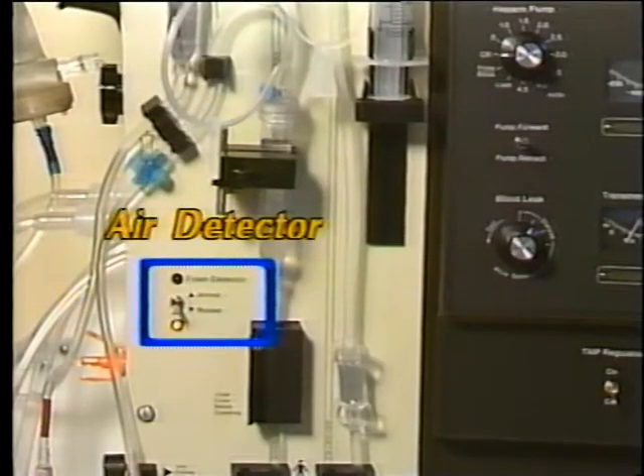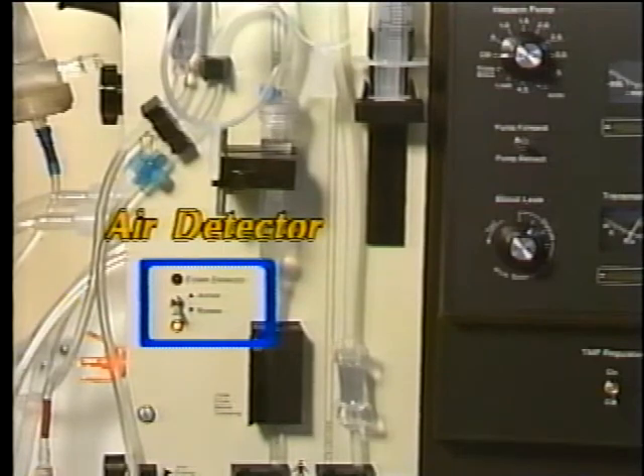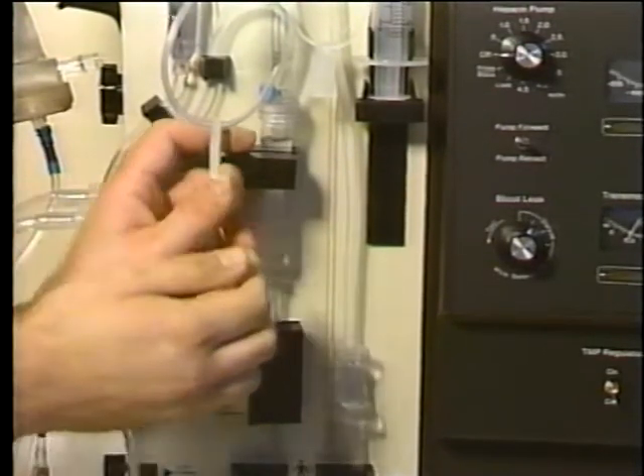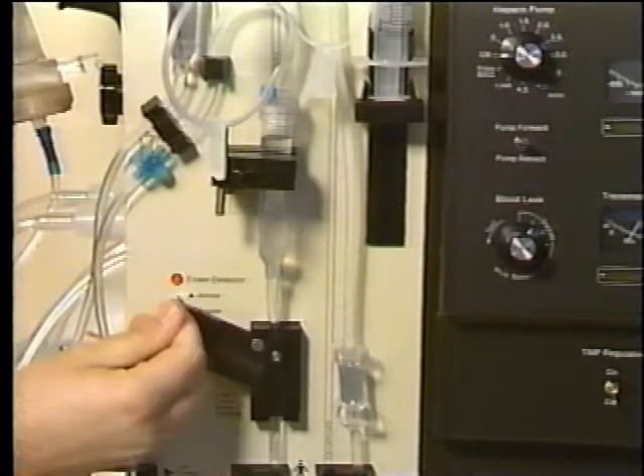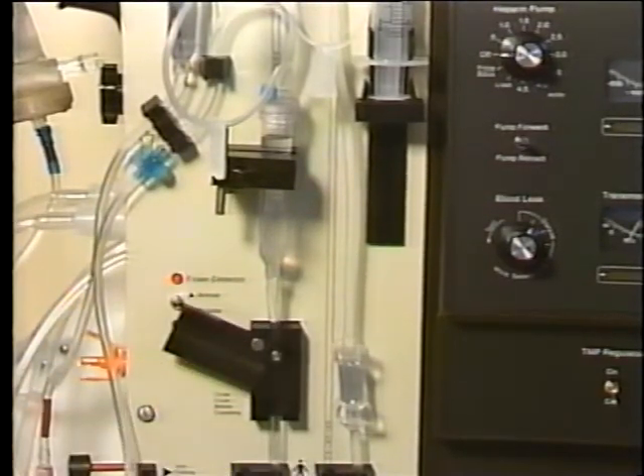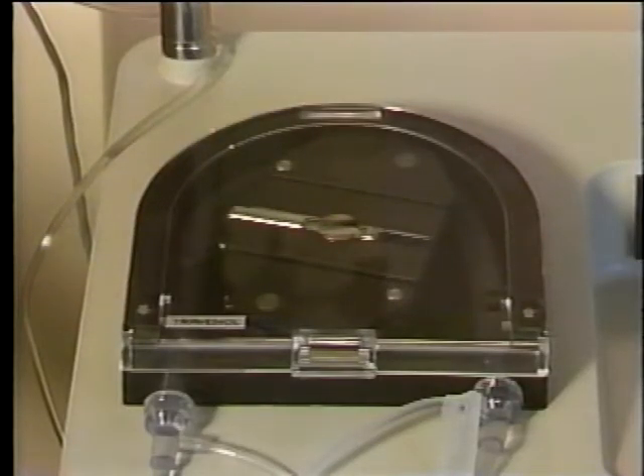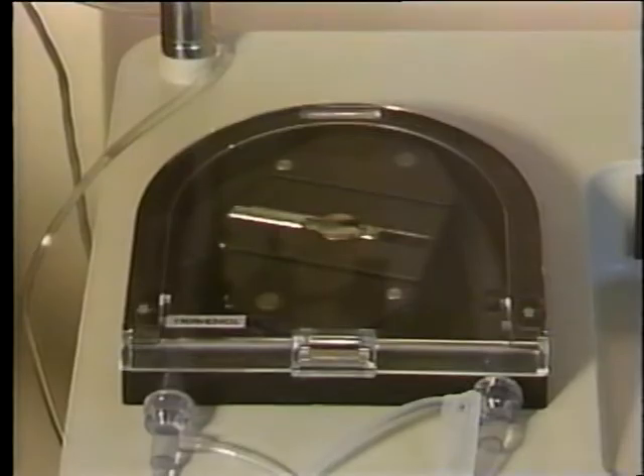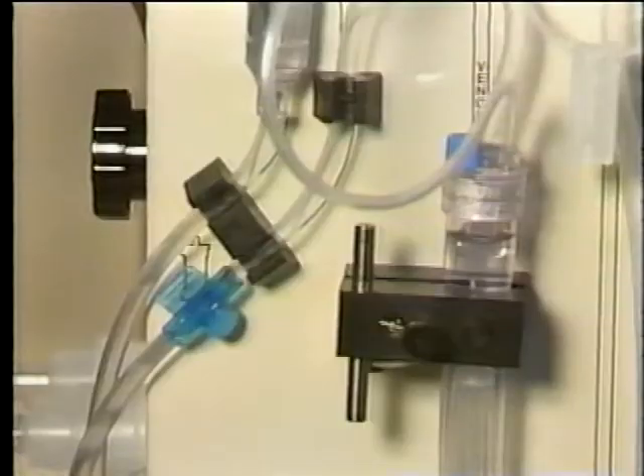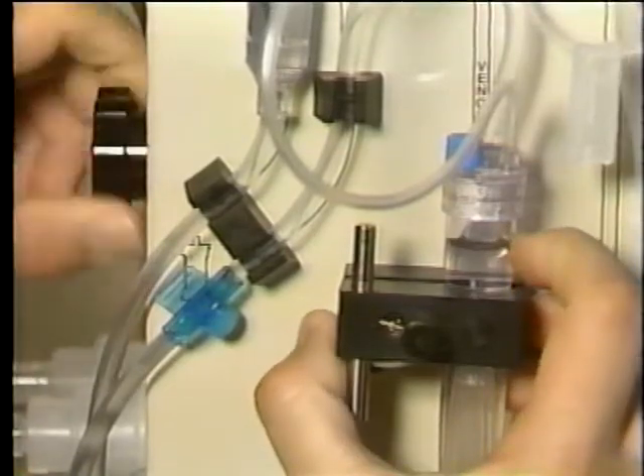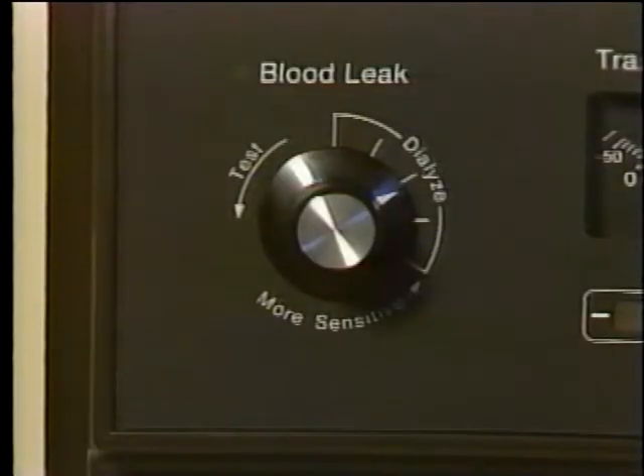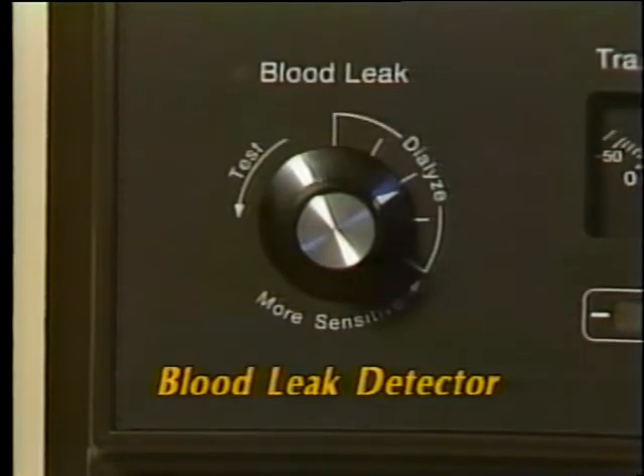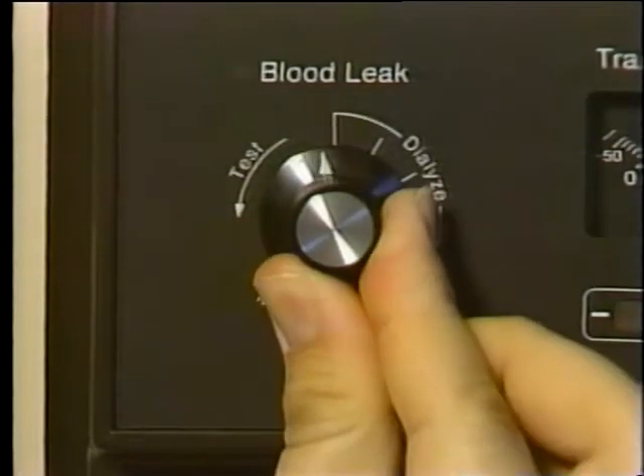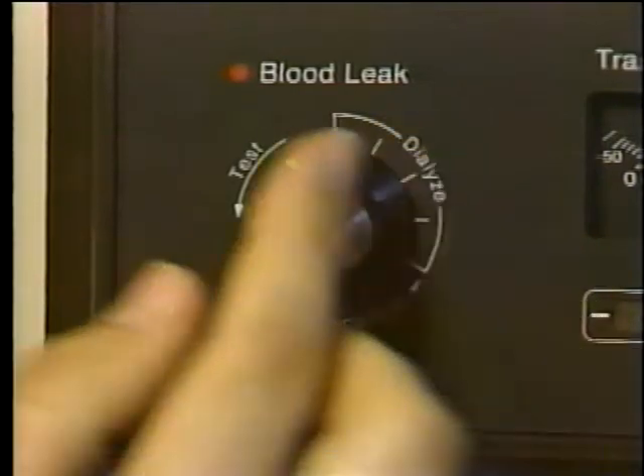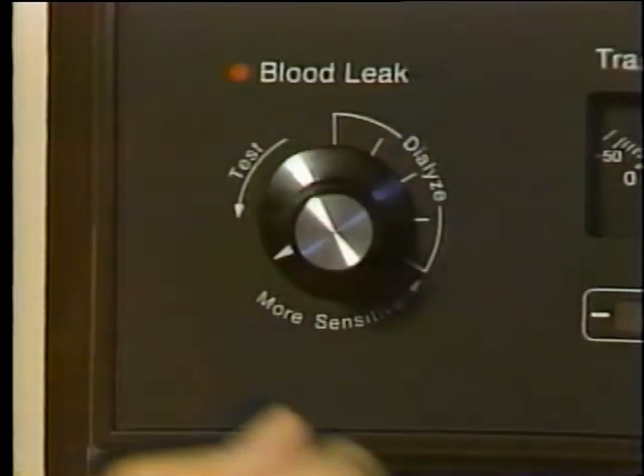The air detector is designed to prevent the patient from being infused with air during dialysis. To test the air detector, place the device in the armed mode and verify its performance. Note that the venous line is clamped, the blood pump is stopped, and that the audible and visual alarms are working. Make sure that the air detector is armed before initiating dialysis. Then adjust sensitivity. The blood leak detector is a sensor that detects red cells in dialysate outflow if a membrane leak occurs. Test the blood leak detector by turning the knob to the test position. You should get audible and visual alarms. Then adjust sensitivity.